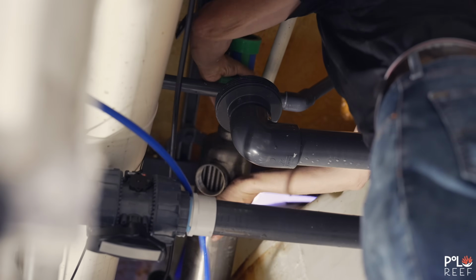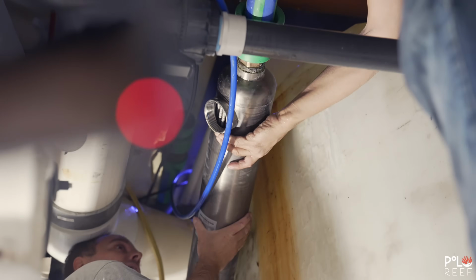Joe and John decide to begin their search starting with the large heat exchanger. So we got the unit out. Now we're going to pull off the fittings from it. We're going to put on some test ports and pressurize it to whatever the manufacturer recommended PSI is, 60, 70 pounds. And then we'll let that sit for a half hour and see if there are any holes in it.